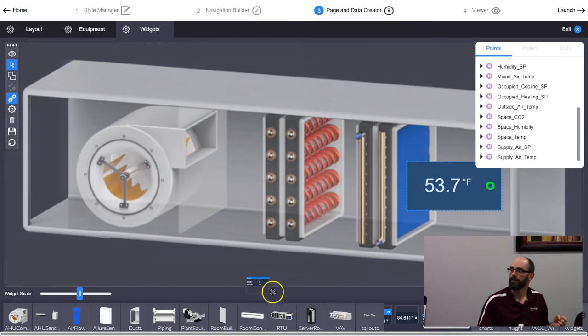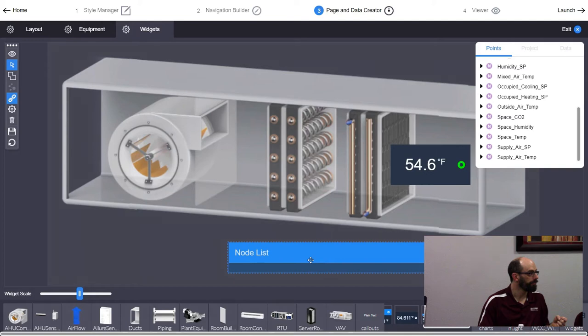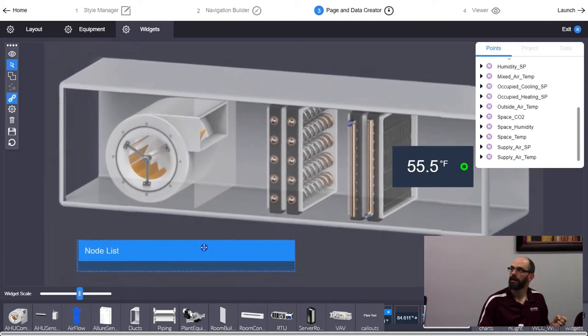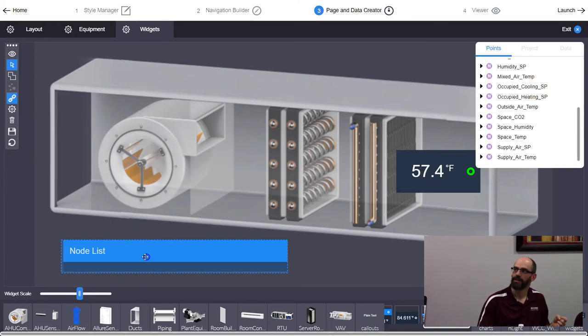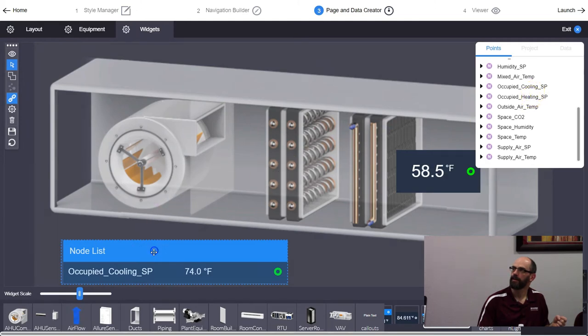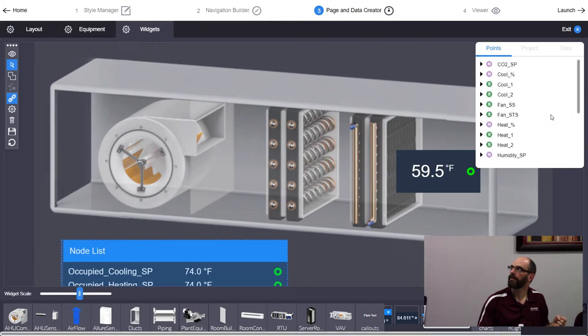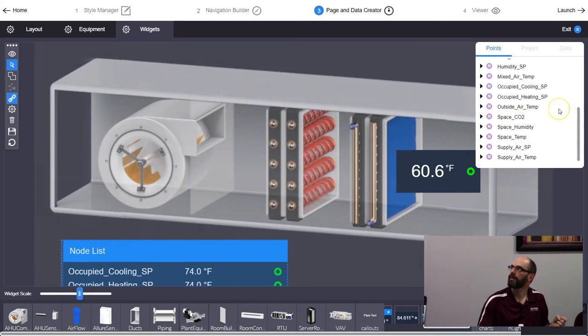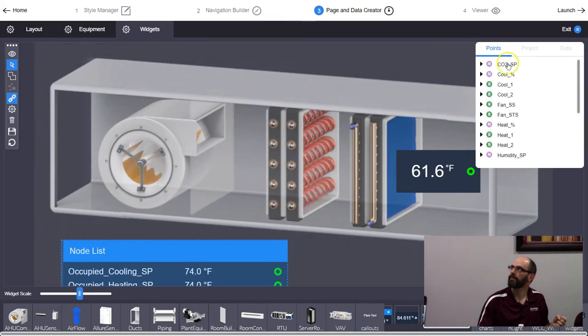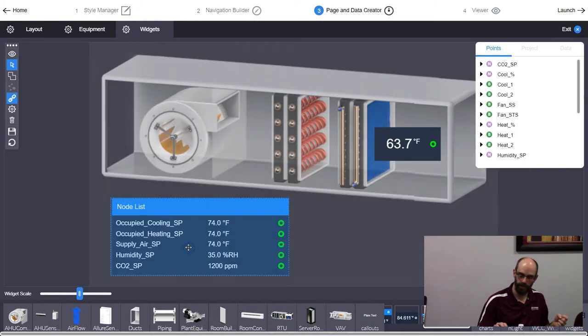To add multiple points, use the node list rather than the node value call-out — otherwise it keeps replacing instead of adding. I'll make a setpoints list: add heating setpoint, cooling setpoint, supply setpoint, CO2 setpoint. You can see when you add items and it grows off the page — click on it and it'll resize for you. Then hit Save.